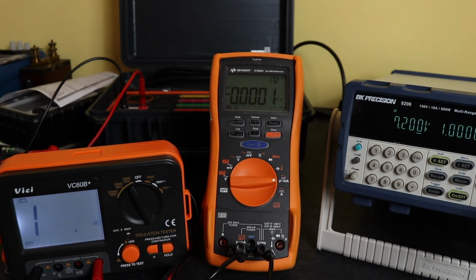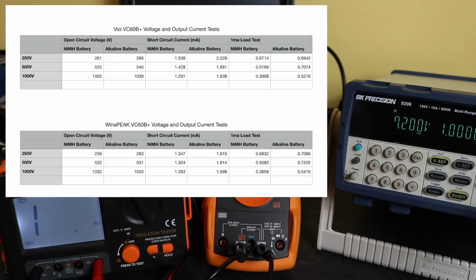So the Vici insulation tester just cannot perform to the IEC standard or the requirements of it, but the WinsPEAK unit is exactly the same. The voltage output drops with the battery voltage, as does the current, and the current output can't reach the required standards either. I'll put this little table up of the various measurements made from each of the units with both an alkaline battery pack and a fully charged metal hydride rechargeable battery pack as well. And you can see, especially with the current output, it falls quite a way below the required 1 milliamp standard.